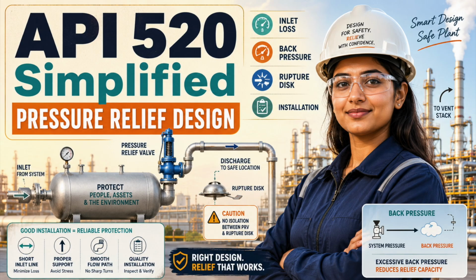You need to know whether those values are constant, variable, or influenced by simultaneous relieving events elsewhere in the plant. A conventional valve may be completely acceptable in one system and completely wrong in another. You should never select it because it is the familiar default.